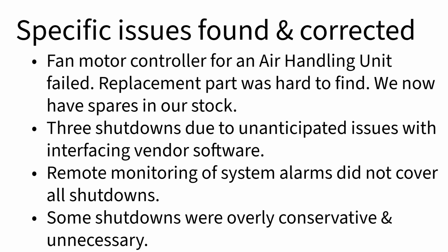Then we had 3 shutdowns that were unanticipated, resulting in a couple of cold Sunday mornings. This was all due to unanticipated issues interfacing vendor software. For example, the air handling unit talks to the building management system, which talks to the heat pumps, and they all should work together to turn the heat pumps on, blow the right amount of air, turn the right amount of heating on the radiators, and so forth. Each of the vendors for each component writes their own code for their unit, and our building management system ties this all together. It's very complicated, and sometimes you just can't anticipate what's going to happen. So there were a couple of instances like that.